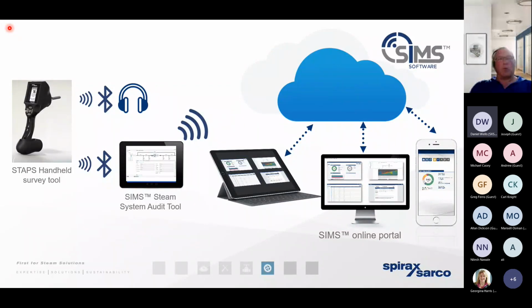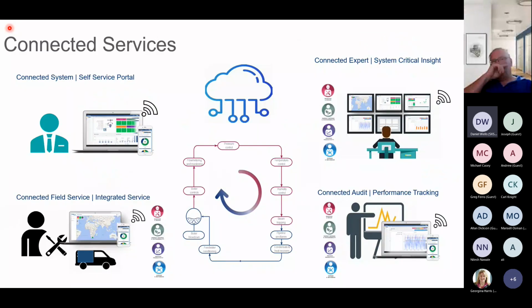And taking the subject of connectivity one step further, we're now able to connect a gateway to a vast number of the solutions that we may have, the different items of capital equipment, not just in the boiler house, but around the wider steam and condensate loop. And the benefit here is traditionally, it may well be some weeks or months until such a time that a maintenance engineer has identified that he thought he had an inefficiency. It may then be a week until a steam expert is able to visit site to verify that. And that steam expert may then have to call upon a service engineer who may need to wait for a number of spare parts before that problem can be identified. There may need to be several visits to and from site, which isn't doing the carbon footprint or the image of the entity in question any favors.